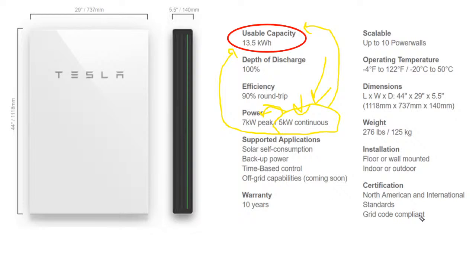A lot of power outages are not more than an hour or so, and so really the main issue with the Tesla Powerwall is its cost - it's expensive. And also 5 kilowatts is just not large enough to run heavy duty electrical devices. An air conditioner runs at a little under 5 kilowatts, and if it's a really hot day and the air conditioner ices up, it has electric defrosters on it that sometimes kick in on a winter setting to provide electric heat as an assist to a heat pump for comfort, not for efficiency. So even though it's a 4 kilowatt continuous air conditioner, sometimes it can surge up to 10 kilowatts, a little more than that. So the Tesla Powerwall by itself is not powerful enough really to run an air conditioner.